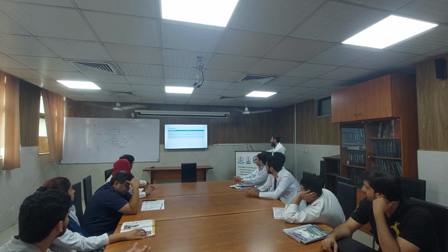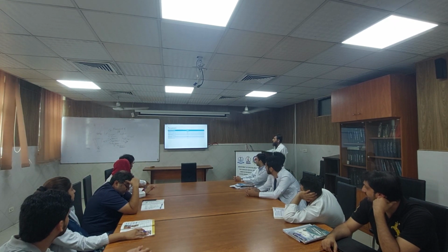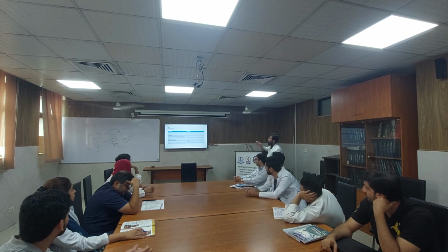Now, what are the parameters? Working substance is Nd-YAG, laser wavelength is 1064 nanometer, pulse energy is from 1 up to 7 millijoules. Laser pulse width is 9 to 21, spot size is circular, and the spot diameter is 1 to 5 millimeter. In iridotomy, we usually prefer an energy of 3 to 8 millijoules. In photomydriasis, 4 to 6 millijoules.